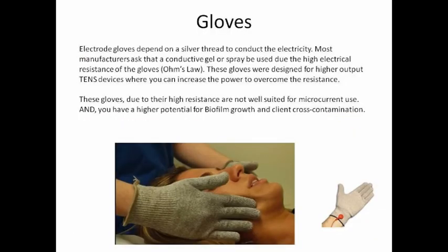Electrode gloves depend on a silver thread to conduct the electricity. Most manufacturers ask that a conductive gel or spray be used due to the high electrical resistance of the gloves, and that's Ohm's law. These gloves were designed for higher output TENS devices where you can increase the power to overcome the skin resistance. These gloves, due to their high resistance, are not well suited for microcurrent use, and you have a higher potential for biofilm growth than you do on the steel wands or probes.